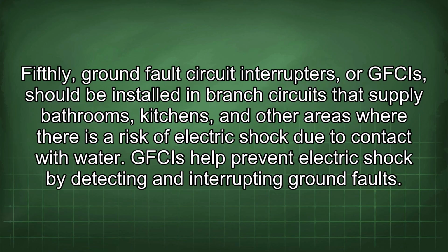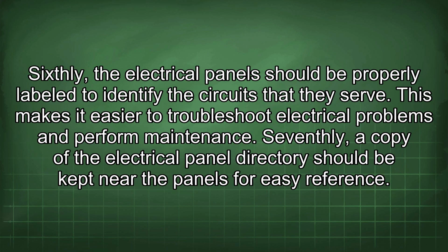Fifthly, ground fault circuit interrupters, or GFCIs, should be installed in branch circuits that supply bathrooms, kitchens, and other areas where there is a risk of electric shock due to contact with water. GFCIs help prevent electric shock by detecting and interrupting ground faults. Sixthly, the electrical panel should be properly labeled to identify the circuits that they serve. This makes it easier to troubleshoot electrical problems and perform maintenance. Seventhly, a copy of the electrical panel directory should be kept near the panels for easy reference.